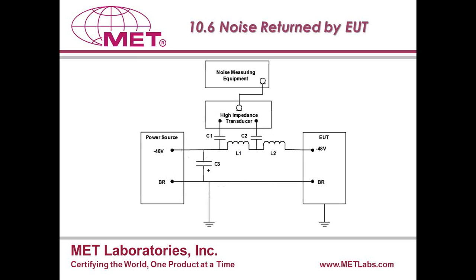So my next slide shows, I borrowed this diagram right out of the 1089, where we can see right next to the capacitors C1 and C2, we have a high impedance transducer. This transducer could be a separate board or a device which could hook up to your noise measurement system, which could very well be a spectrum analyzer with 50 ohm input or not. In some cases, some of the Agilent spectrum analyzer models already give you the built-in option where you can choose between 50 ohm and 1 megaohm impedances. I highly recommend the use of those spectrum analyzers which have the built-in feature of 1 megaohm, for consistency's sake.